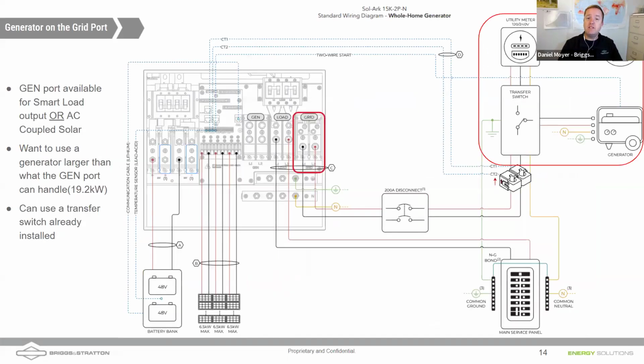Another opportunity to bring in a generator is also on the grid port. Sol-Ark, I believe, is one of the best inverters on the market for integrating generators. And here's the example why: if you do have a generator on the grid port and the solar is producing, you don't want to go in there every time and maybe disable grid sell, right? The idea is that you're going to start backfeeding the grid. Once the generator starts, as far as the Sol-Ark is concerned, it sees the grid there. It may try to start backfeeding the generator. You don't want to see a generator run backwards. The Sol-Ark, though, is smart enough to know that it sees the generator there by recognizing that when it does start to backfeed, the voltage and the frequency of what it would expect during a nominal backfeed event isn't there, and it will then prevent and curtail that backfeeding.